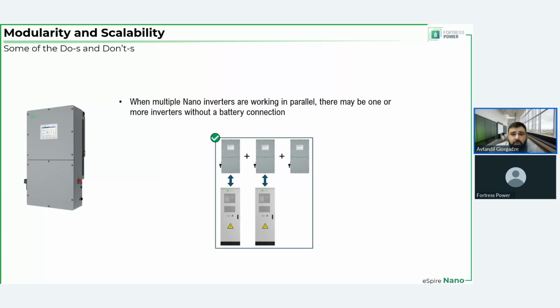When multiple Nano inverters are working in parallel, there may be 1 or more inverters without a battery connection. I mentioned this already, but again, this is appropriate. You can have 1 or more inverters in the parallel group without any batteries. Why you want to do that is a different matter. Maybe you are not going to need any more storage now, but you have plenty of PV, and you are expecting that later down the road, in about 2 or 3 years, you're going to add another battery, and you want to reserve that ability to utilize all the PV that you have and have the system ready for the battery side expansion.